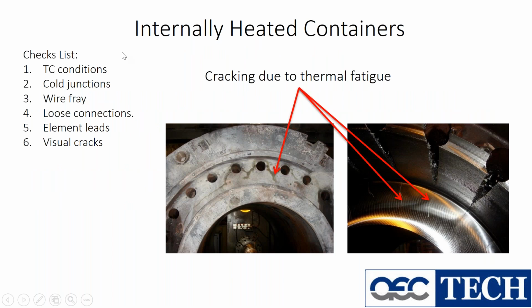If you're going to have these types of systems, take a look and see if you notice anything visual. You know, when you go get your oil change at a quickie lube place, they just walk around the car, flick your lights, some of the simple things. We want to look to see if there's any broken TC connections, cold junctions, wire frays, loose connections, loose element leads. Those types of things are going to contribute to unscheduled downtime, and that's what we're trying to avoid. Look for visual cracks.